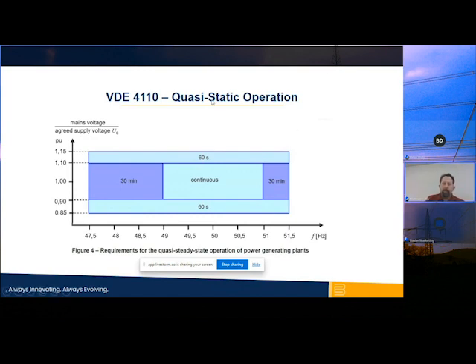So the continuous operation mode is basically running plus or minus 10% voltage, so 1.1 per unit down to 0.9 per unit of voltage. That's what we consider normal operation. Likewise with the frequency, we're going to operate between 49 and 51 hertz, so plus or minus one cycle of our nominal. Within those realms, we're in our normal continuous operation. But what we want to look at are the situations beyond that.